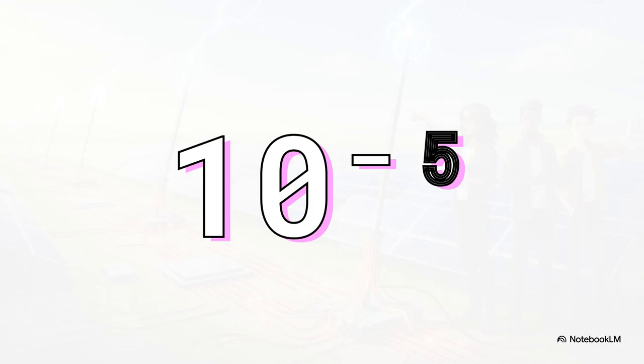Now, here's where it gets really important. You have to compare your calculated total risk to this magic threshold right here, 10 to the power of -5. When you calculate your total risk of human life loss, known as R1, you compare it to this tolerable limit set by the IEC standard. If your calculated R1 is less than or equal to 10 to the -5, great, no mandatory LPS is needed. But if your risk exceeds 0.00001, an LPS is strictly required, no exceptions.